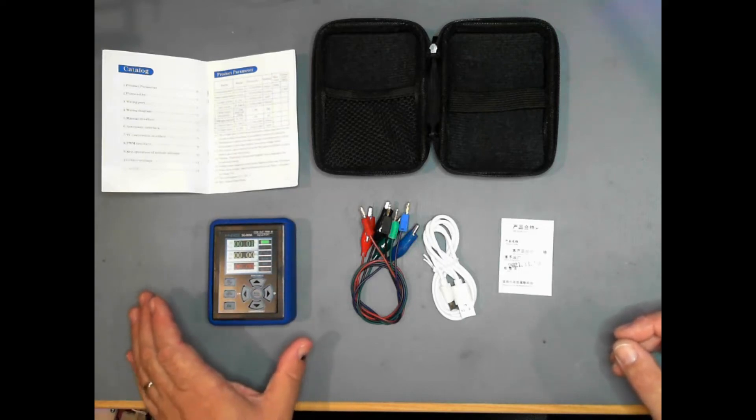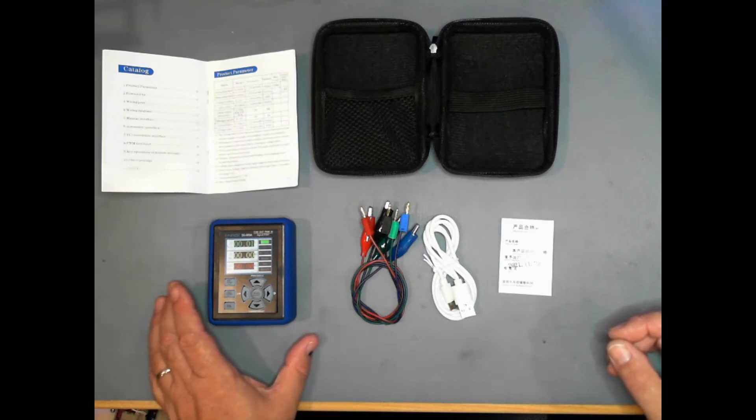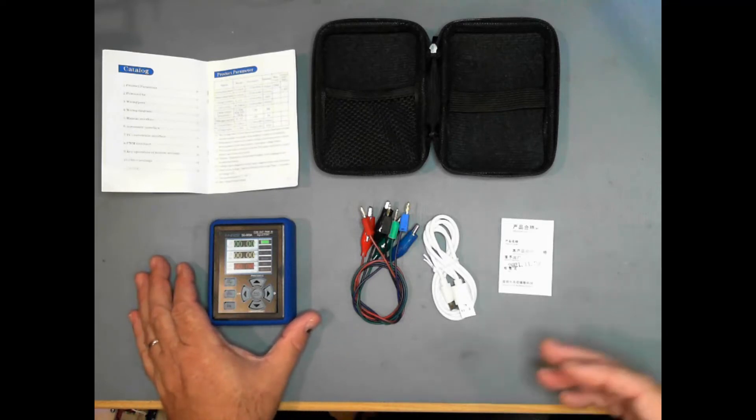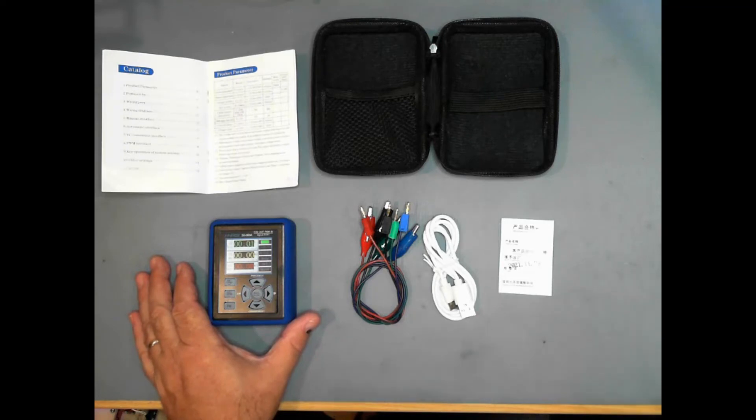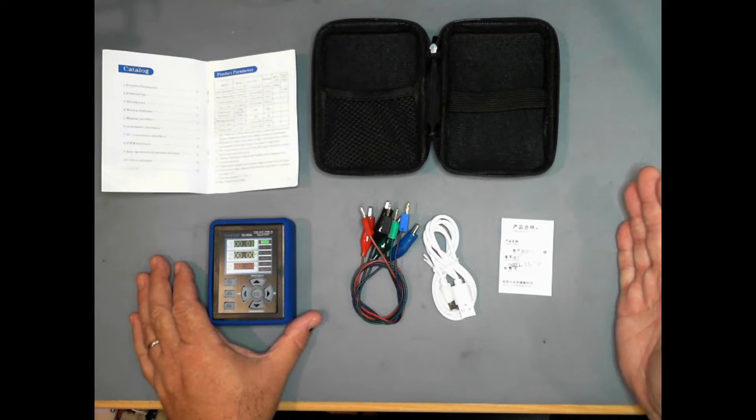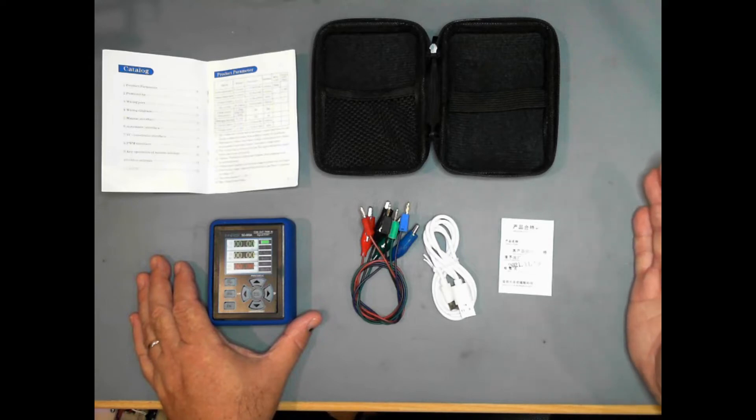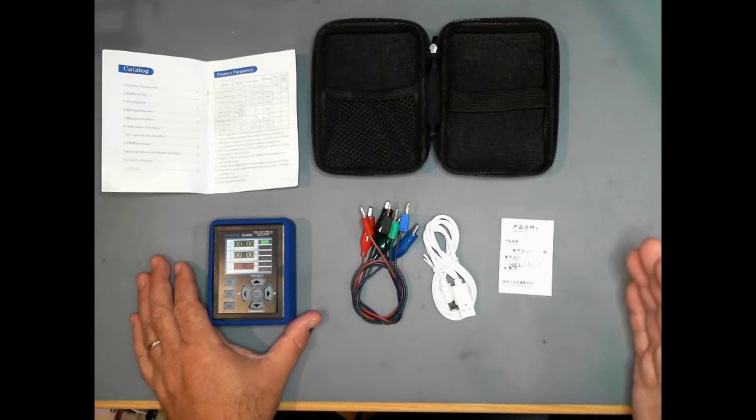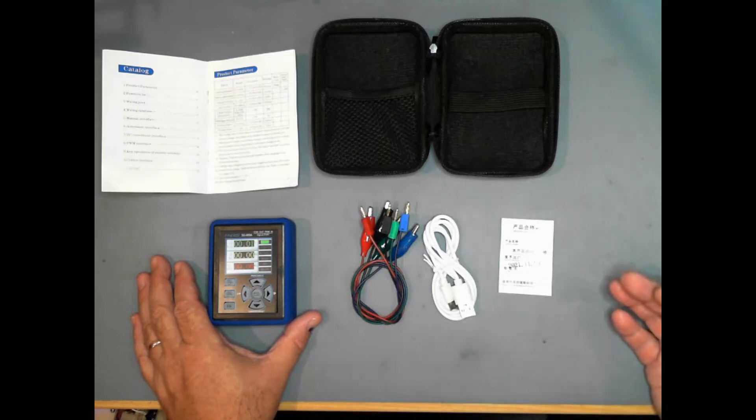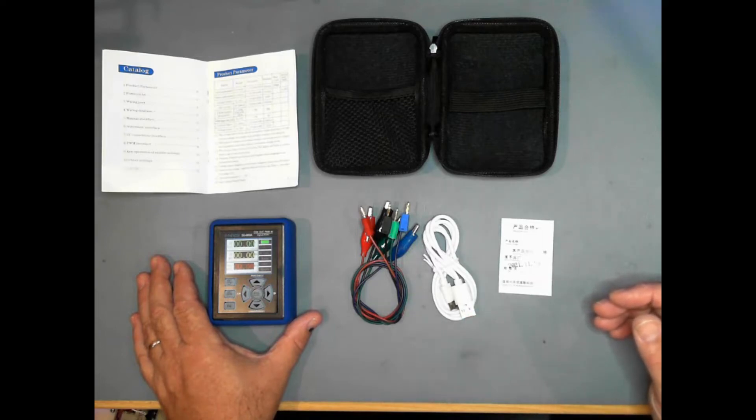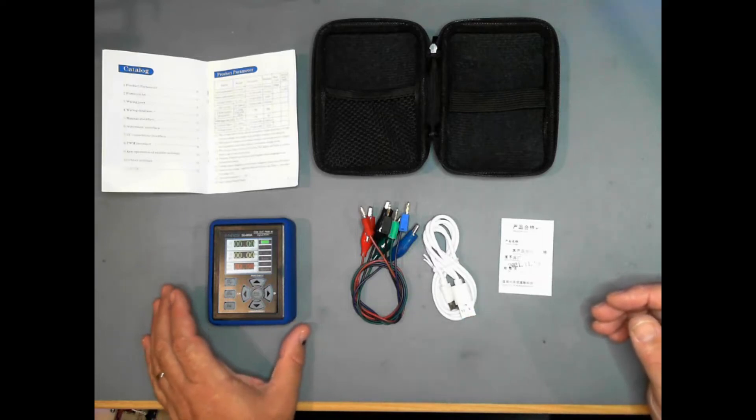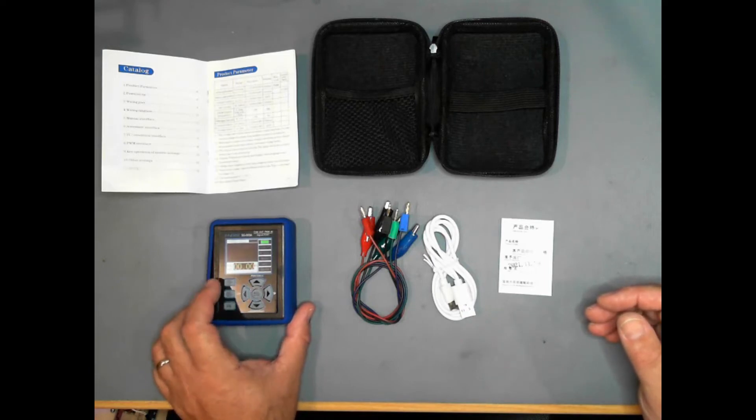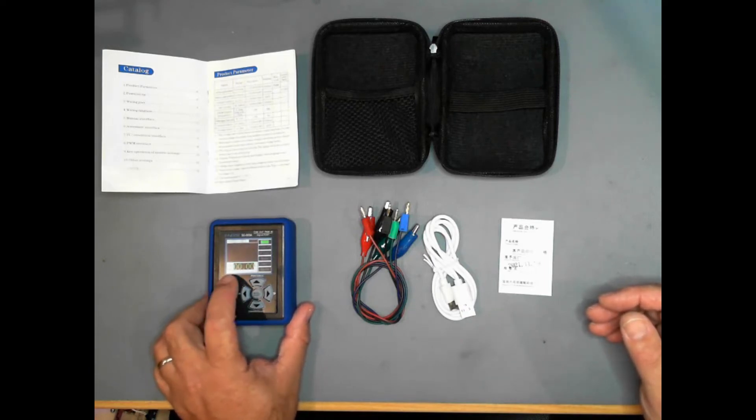You get the device itself and it's actually a nice clear display, but it's not a very intuitive display. I have managed to work through a number of the settings. It will loop power, so it will power the loop. I have actually connected it to a pressure sensor, in this case it was a low value pressure sensor. It powered the sensor and I was able to get a feedback and see the current changing. I think it's actually going to be very useful once I get a handle on driving it properly.